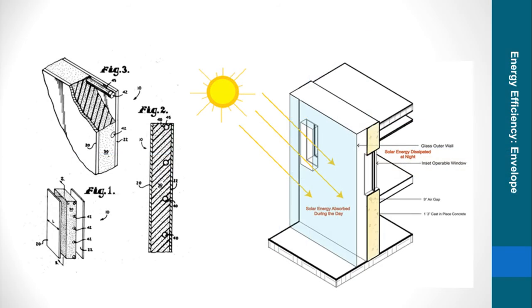Structural insulated panels were selected for the primary exterior wall type due to their superior thermal insulation, ease of construction, and ease of transport to the remote island. To further enhance the performance of the SIPs, pipes containing phase change materials are embedded in the insulation layer. Phase change materials absorb and release thermal energy as they freeze and melt, allowing the SIPs to act as a thermal mass. This building is perfect for the first application of this emerging technology, as the cold but mild climate makes thermal mass a highly appropriate design strategy.